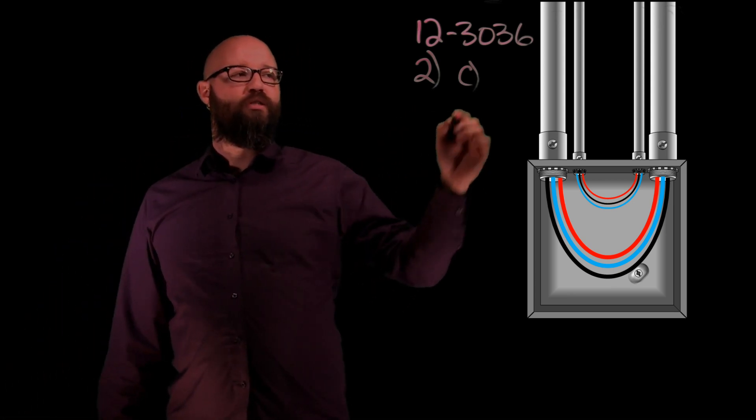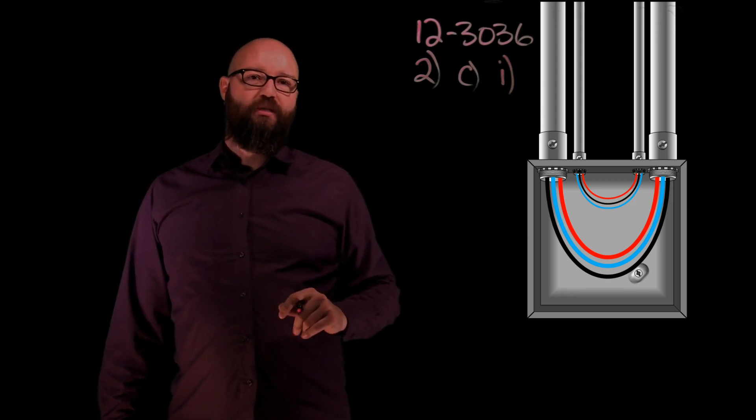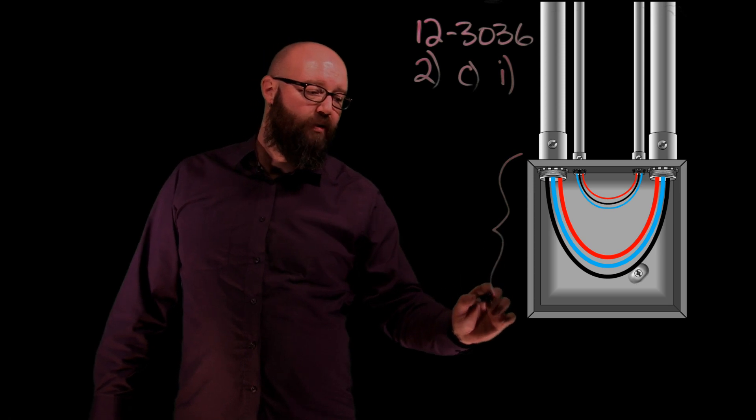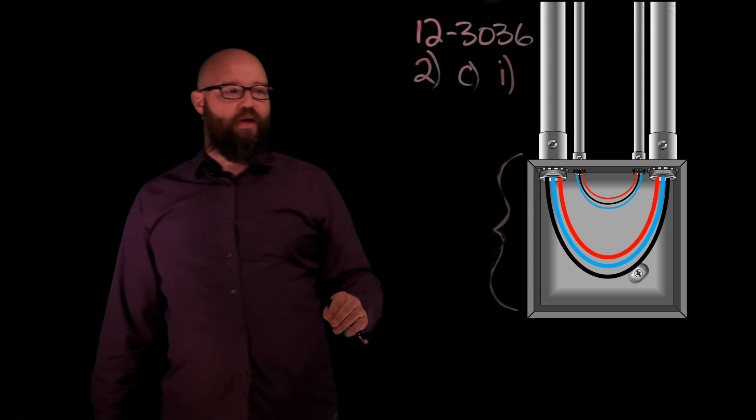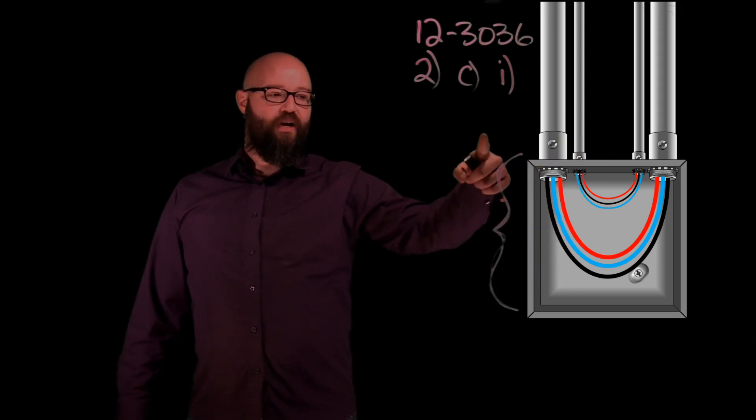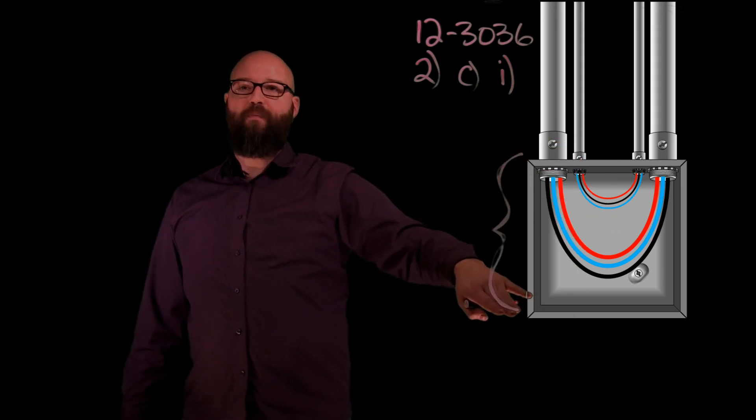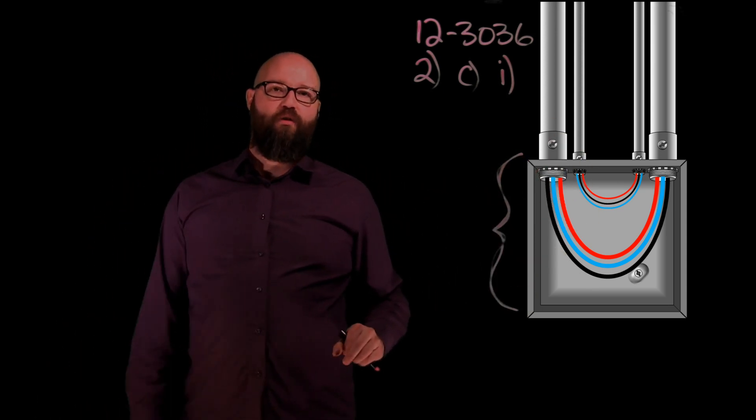But if we take a look at item 2C and specifically after the C item I, what we're actually going to be sizing is the dimension of this wall right here on our pull box. We want to make sure that we have enough distance between the wall that our conduits enter and the opposite wall so that we can observe proper bend radiuses for our conductors and we're not coming in too tight on those.